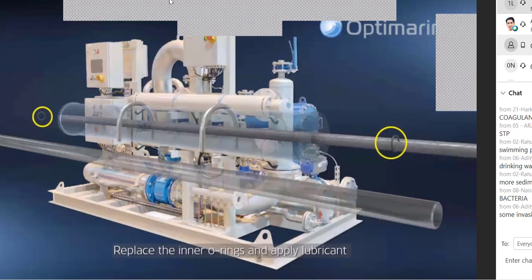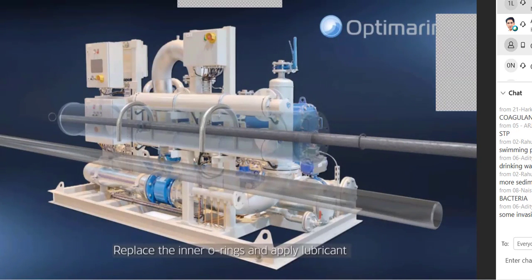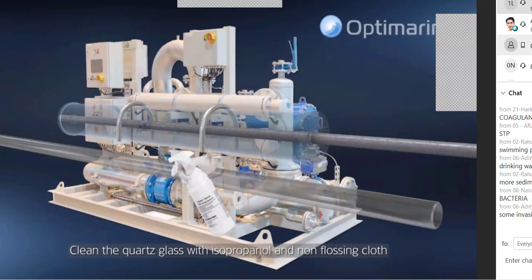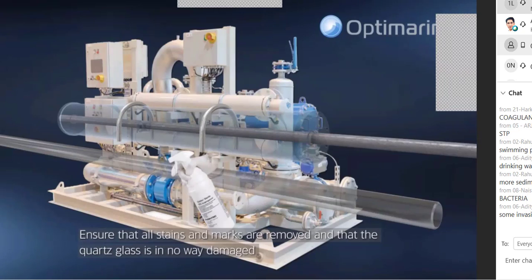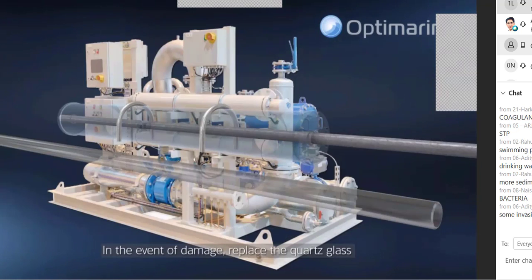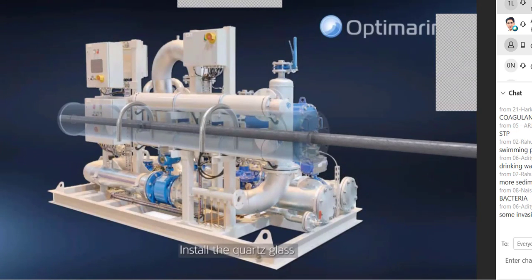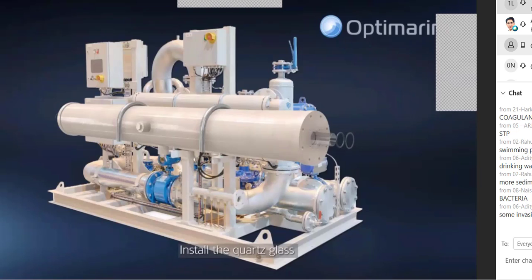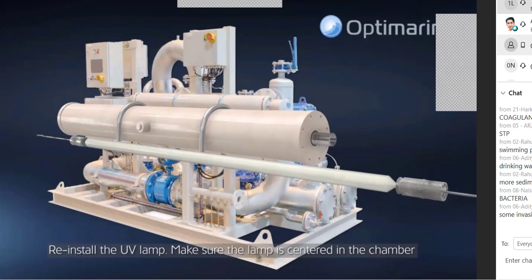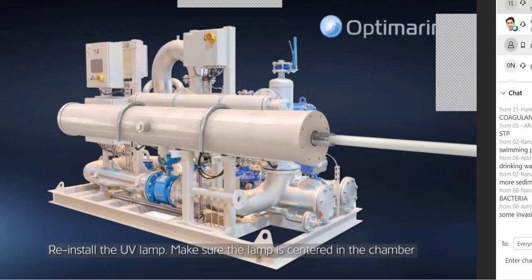Replace the inner O-rings and apply lubricant. Clean the quartz glass with isopropanol and a non-flossing cloth. Ensure that all stains and marks are removed, and that the quartz glass is in no way damaged. In the event of damage, replace the quartz glass. Install the quartz glass. Reinstall the UV lamp. Make sure the lamp is centered in the chamber.